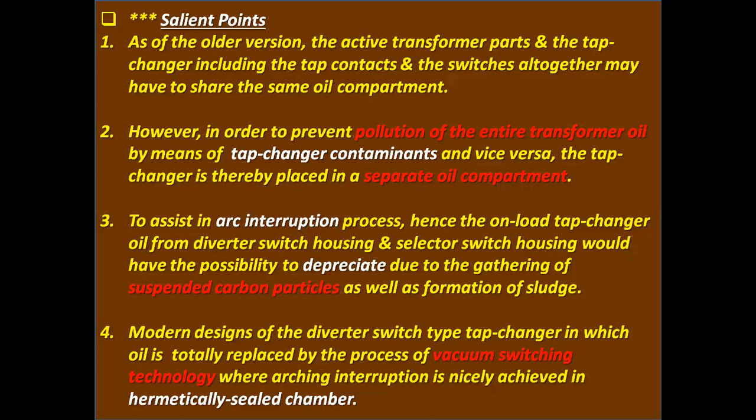Number three, to assist in the arc interruption process, the on-load tap changer oil from the diverter switch housing and selector switch housing may depreciate due to the gathering of suspended carbon particles as well as formation of sludge.